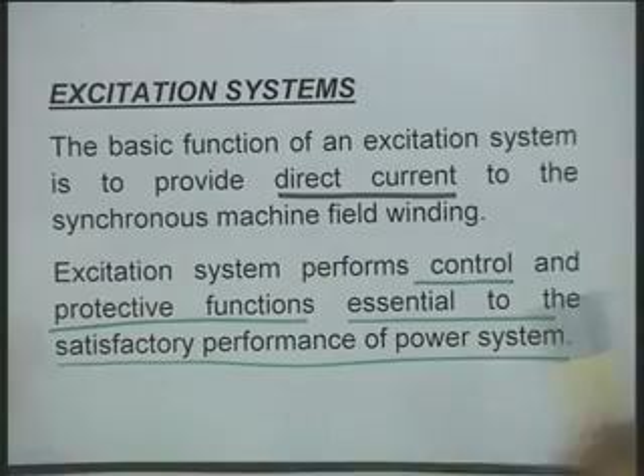As I told you, there are two kinds of functions: control functions and protection functions. Now, what are these control functions? Let us see. Control functions are basically control of voltage and reactive power flow. In the excitation system we provide various controls so that we can maintain the terminal voltage constant under varying load conditions.